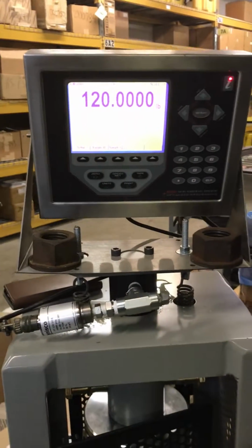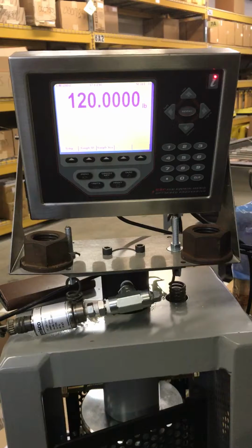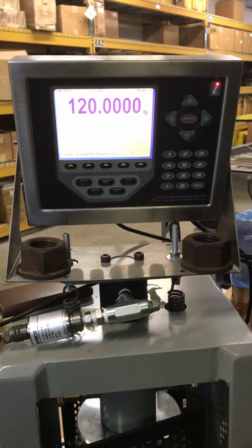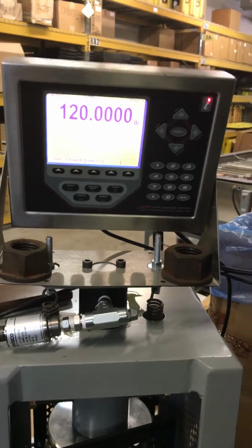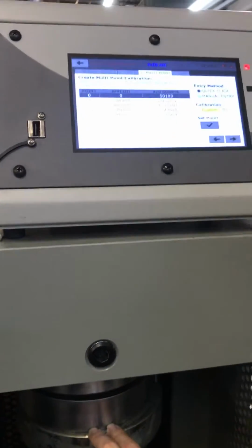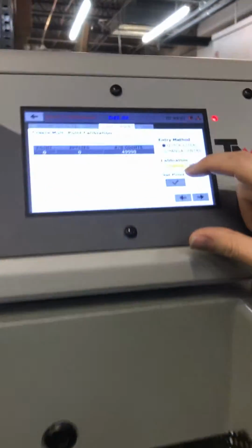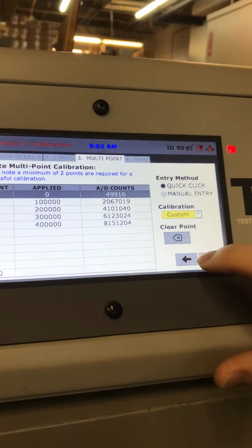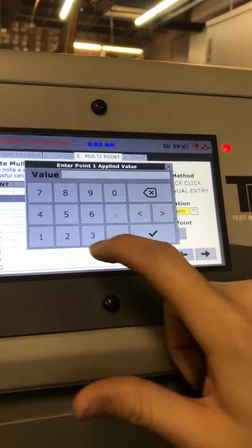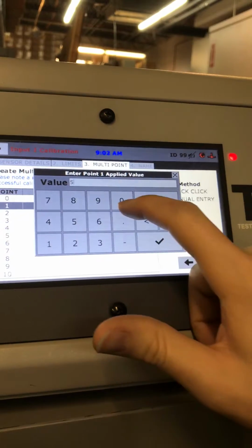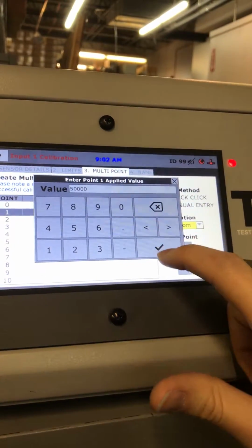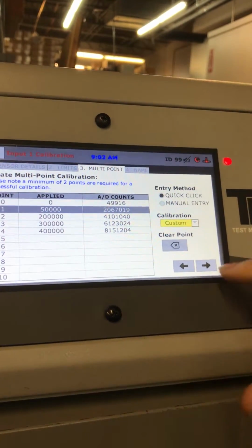We have this set up. Here's our monitor that's showing us. This is our calibration instrument for these purposes. So we'll say that this is our 0 point. We'll set that. And then we'll say we want to start at 50,000. We want to set a first point at 50,000 pounds-force.